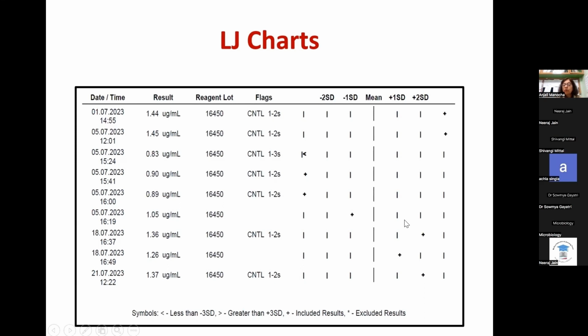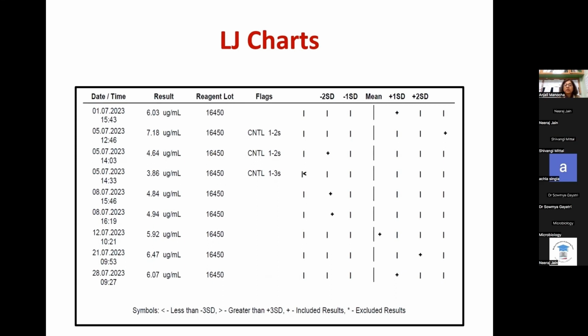So here there is something wrong with the methodology or the reagent. So this requires a proper root cause analysis. Again, one of those pretty bad LJ charts which has to have a complete root cause analysis and documentation of the corrective action taken and verification of the corrective action, which is very, very important after such an LJ chart.